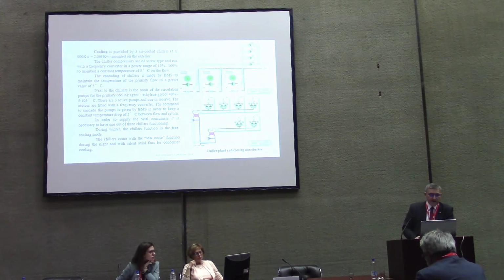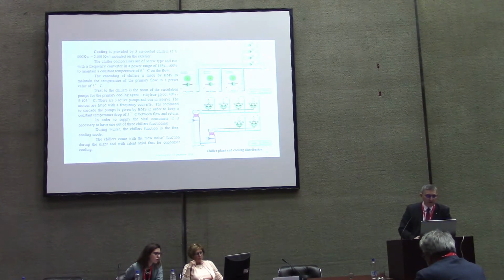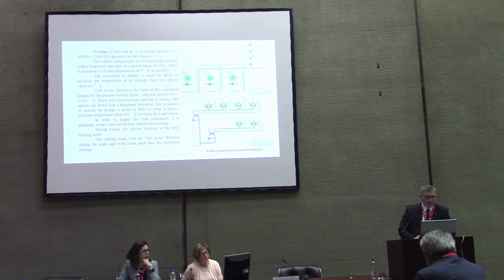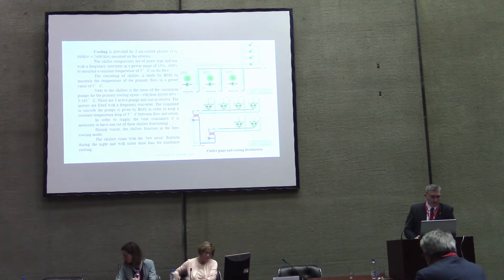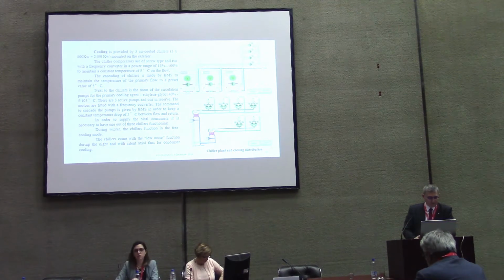The cooling is provided by 3 air-cooled chillers. The capacity is 2,400 kilowatt, mounted in the exterior. The chiller compressors are of screw type and run with a frequency converter in a power range of 50% to 100%, to maintain a constant temperature of 5 degrees on the flow. Of course, we have the BMS and the chillers working in cascade. Next to the chillers is the room of the circulation pumps for the primary cooling agent, ethylene glycol 40%, working between 5 and 10 degrees Celsius. There are 3 active pumps and 1 on reserve.